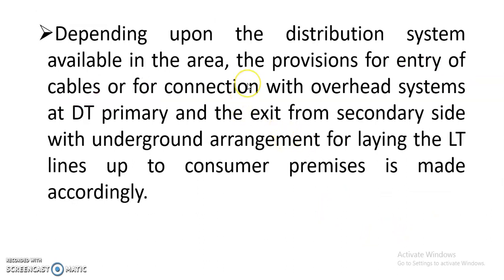Then depending upon the distribution system available in a particular area, the provision for the entry of the supply cable or connection with the overhead system at the distribution transformer primary, and the exit from the secondary side, that is the LV side, with the underground arrangement for laying the LT cable or line up to the consumer premises, is made accordingly, depending on the requirement. Whether it is required underground or overhead, either it can use LT cable or LT lines, which use a distributor.